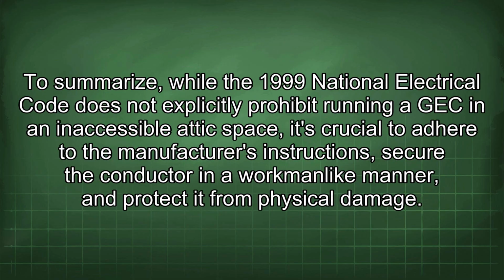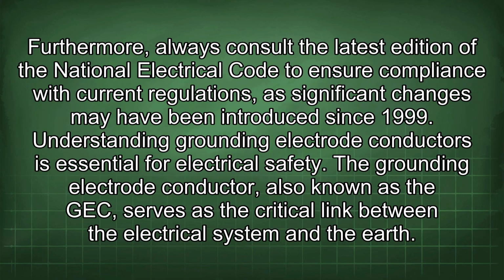To summarize, while the 1999 National Electrical Code does not explicitly prohibit running a GEC in an inaccessible attic space, it's crucial to adhere to the manufacturer's instructions, secure the conductor in a workmanlike manner, and protect it from physical damage. Furthermore, always consult the latest edition of the National Electrical Code to ensure compliance with current regulations, as significant changes may have been introduced since 1999.